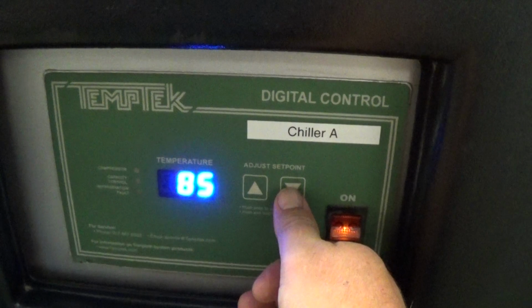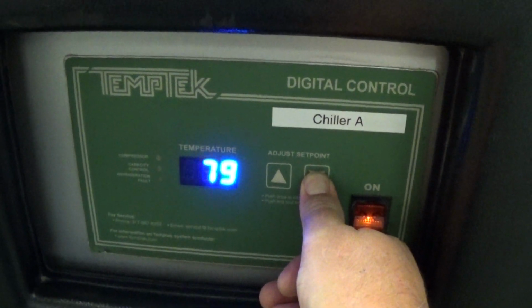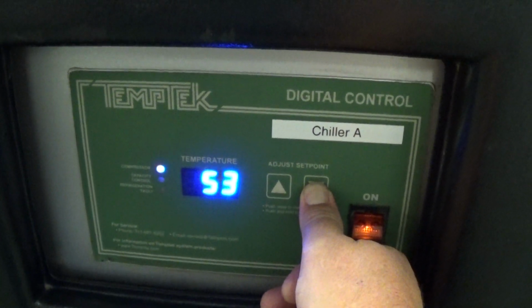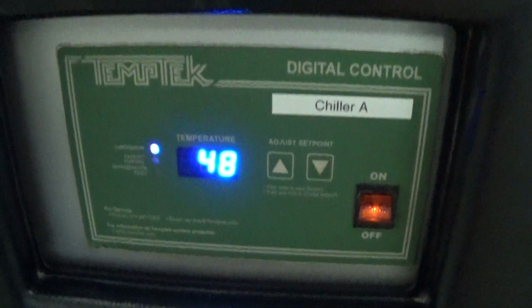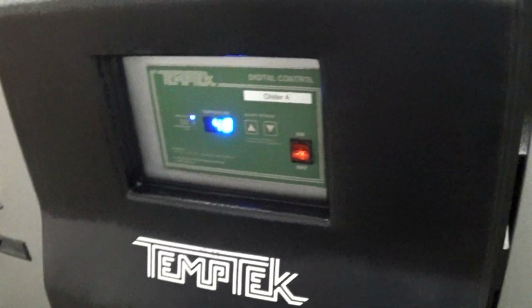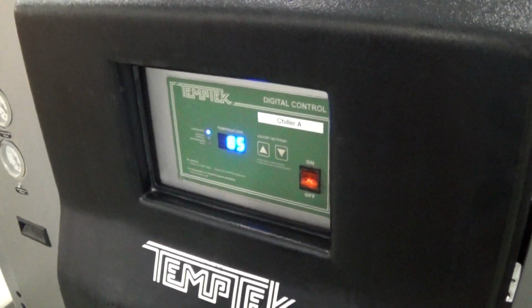And this is the simplest controller they make. You just press the down button, and we get a lower limit of 48. Anything below 48 degrees, you would need to run a glycol mixture and consult with us how to make that change.